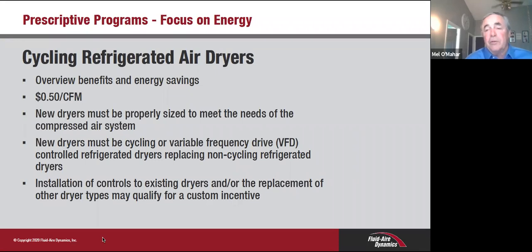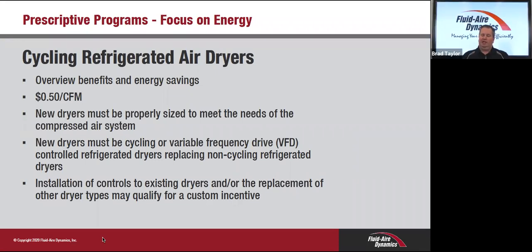And for those of you that leave your compressed air dryers on overnight when you're not running production, cycling is another way to add some shutdown or standby capability, since it'll shut down for a majority of the time because there's no heat load on that dryer. So a great point, Mel.